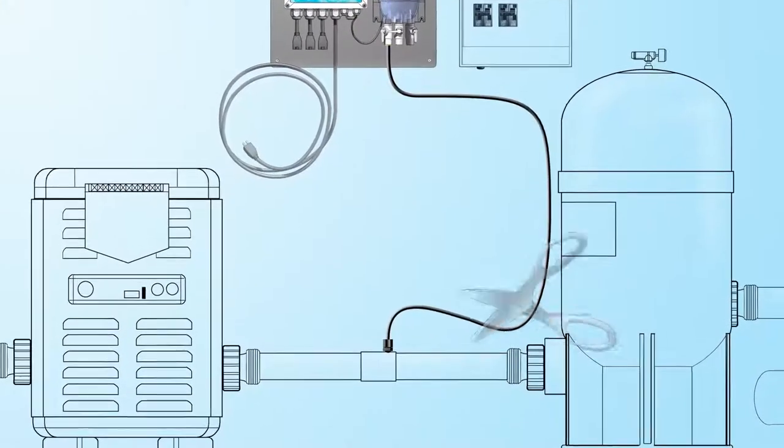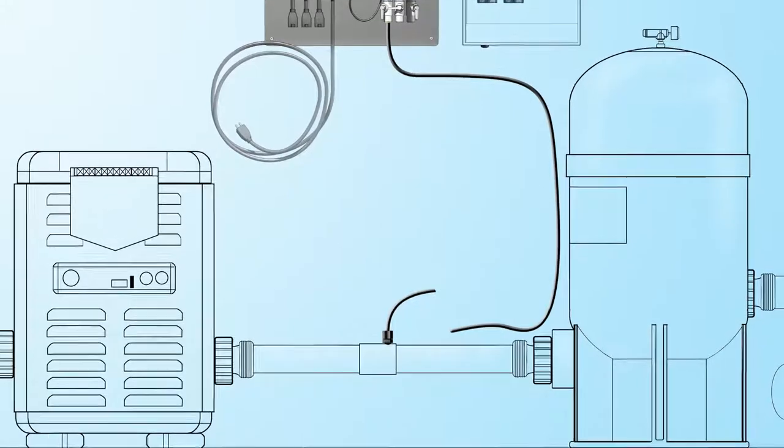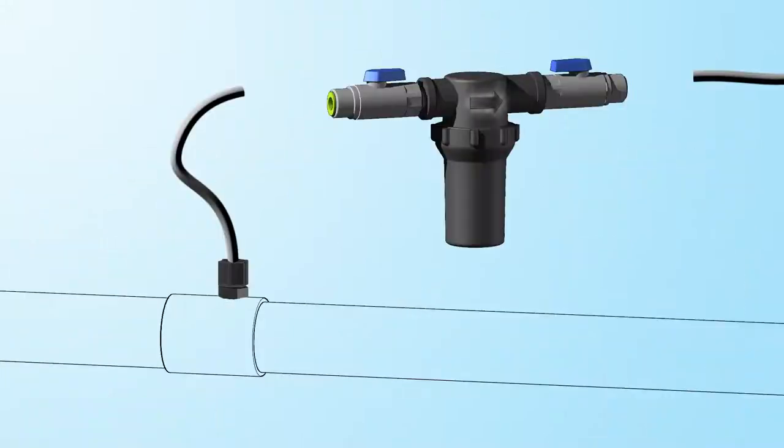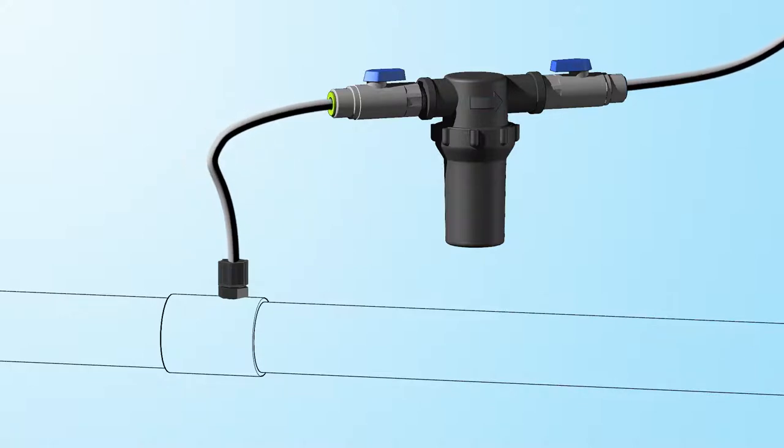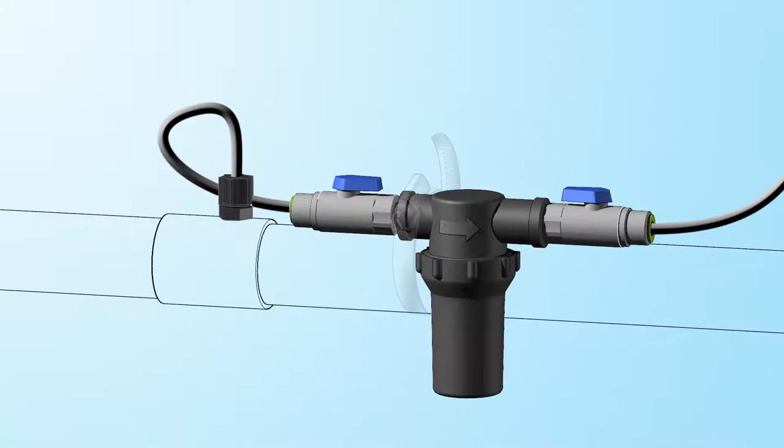To install the inline strainer, cut the tubing. Orient the strainer so that the arrows on the top are pointing in the direction of the flow of water, away from the pipe, and toward the flow cell. Insert the ends of the tubing into the valves on either end of the strainer. Using the hose clamps, secure the strainer to a pipe.